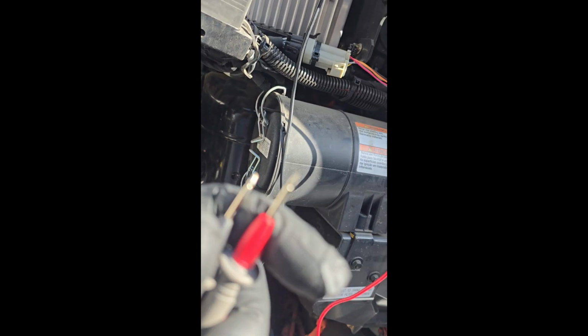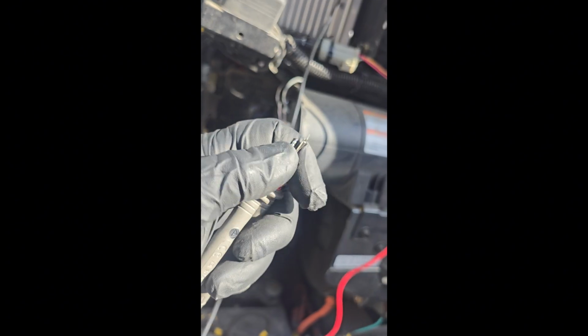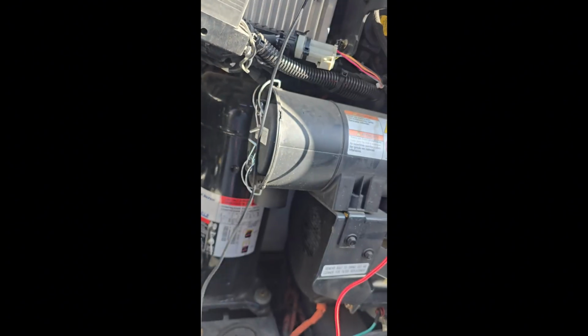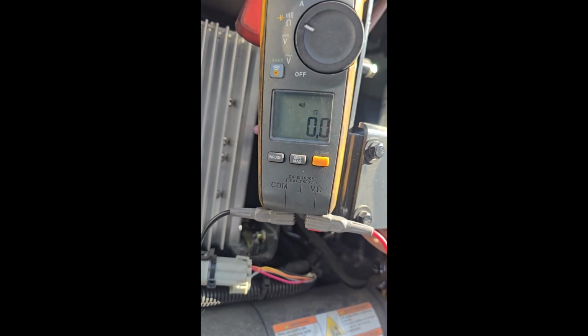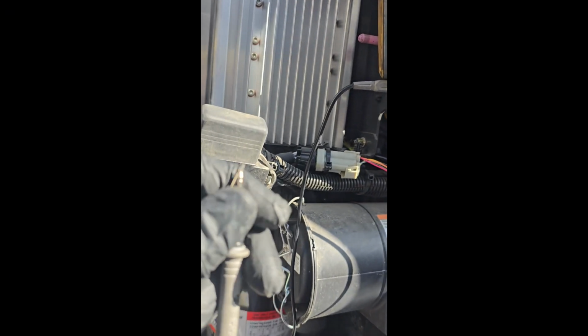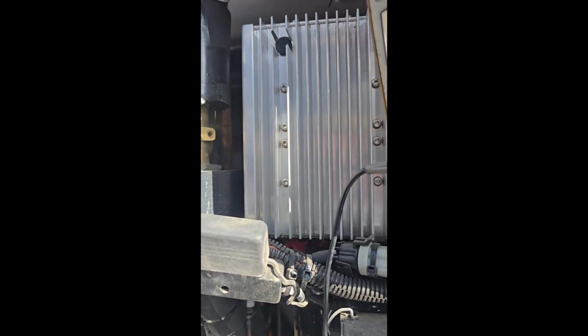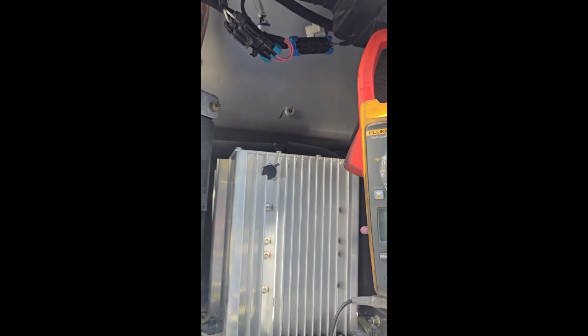And if I take my leads here and touch them together, see that? We have infinite resistance. So that fan motor, the IP circuit in the fan motor, is considered defective or faulty.